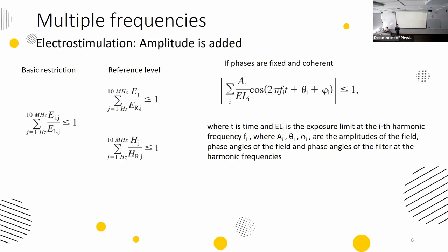What if a device is not working at only one frequency, but has a spectrum of frequencies working simultaneously? For electrostimulation effects below 10 MHz, you need to add amplitudes, because basic restrictions and reference levels are expressed in terms of amplitudes. So you just add the spectral components. If you have a wideband signal, you apply a Fourier transform to get the spectral components and add them together.